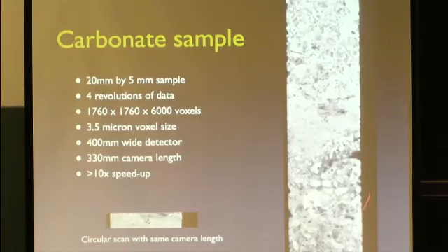This is one of our helical scans using this geometry. It's a 5mm sample, and if we used a single circular scan, this is the height we could reconstruct with this geometry, while staying within the 10 degrees cone angle restriction.